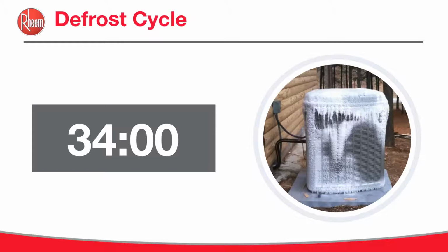Also for defrost, and again, different models operate a little differently on defrost. I'm not saying all models are going to operate the same way. Again, we have training materials on all this, on how the unit's operating. So first on this one, the board will enter a 30-second time delay. This is called a noise abatement, so you're not switching automatically. And in this case, the outdoor fan and reversing valve will be de-energized. A 24-volt signal is then sent through the D terminal for auxiliary heat, if you have auxiliary heat.